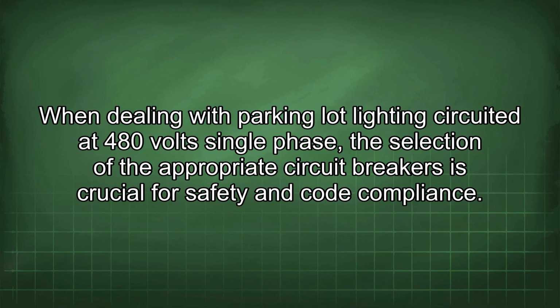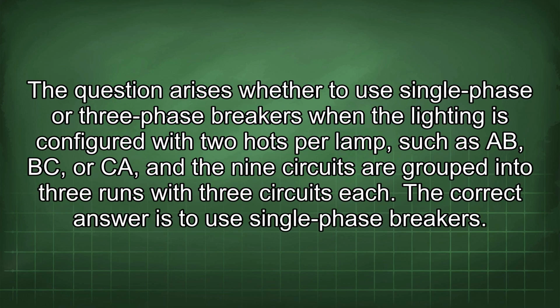When dealing with parking lot lighting circuited at 480 volt single phase, the selection of the appropriate circuit breakers is crucial for safety and code compliance. The question arises whether to use single phase or three phase breakers when the lighting is configured with 2 hots per lamp, such as AB, BC, or CA, and the 9 circuits are grouped into 3 runs with 3 circuits each. The correct answer is to use single phase breakers.